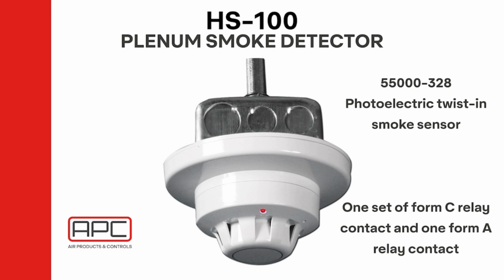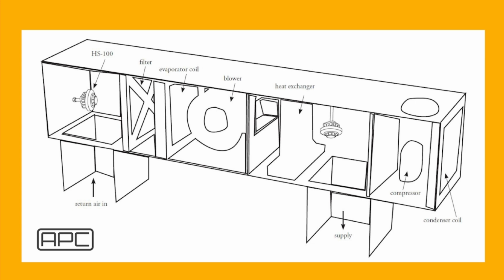Offered in photoelectric models, the heads are interchangeable. As with the other Air Products and Controls duct detectors, the HS100 is universal voltage in 24 volts AC and DC, 115 volts AC, or 230 volts AC. Instead of using sampling tubes, this unit is mounted inside the ductwork. There is a board on the base of the unit to wire the AHU like a standard duct detector. Unlike competitor models, this unit comes as one unit out of the box and has the capability to wire all of the APC remote accessories, including remote test stations.